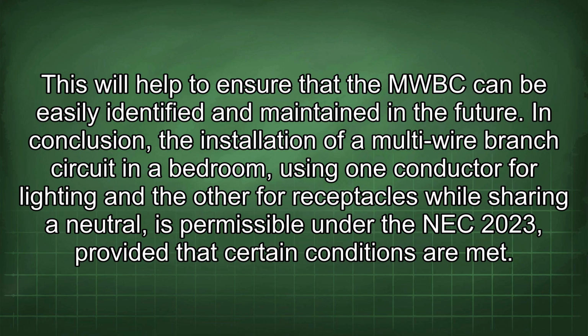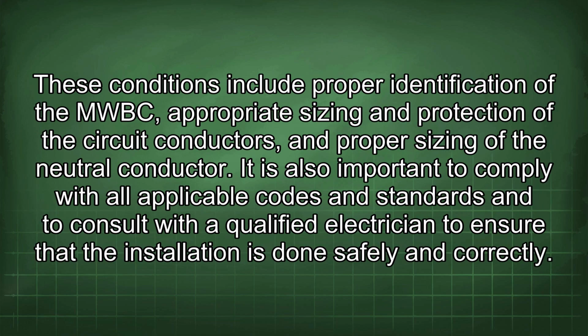In conclusion, the installation of a multi-wire branch circuit in a bedroom, using one conductor for lighting and the other for receptacles while sharing a neutral, is permissible under the NEC 2023, provided that certain conditions are met. These conditions include proper identification of the MWBC, appropriate sizing and protection of the circuit conductors, and proper sizing of the neutral conductor. It is also important to comply with all applicable codes and standards and to consult with a qualified electrician to ensure that the installation is done safely and correctly.